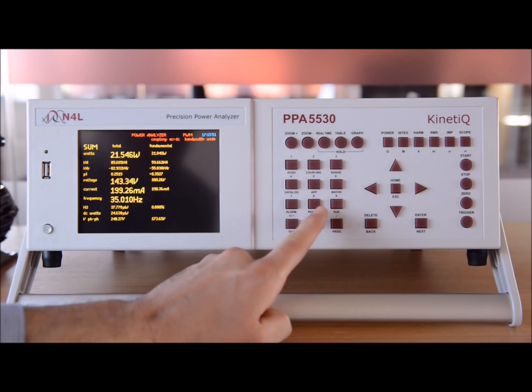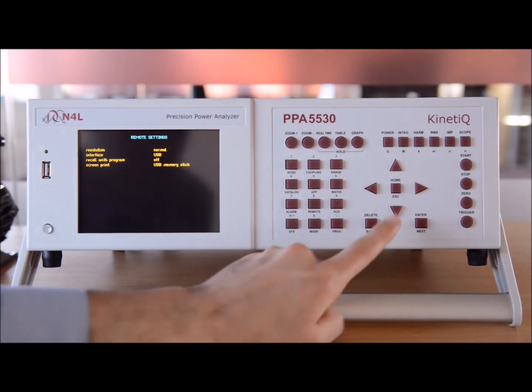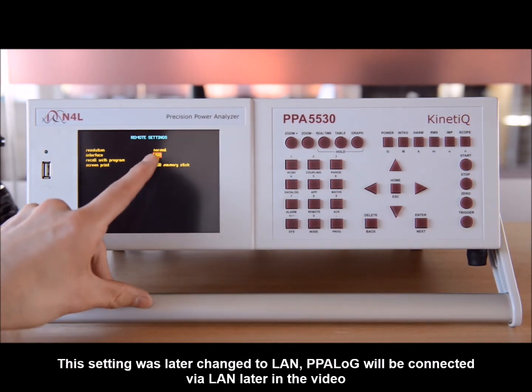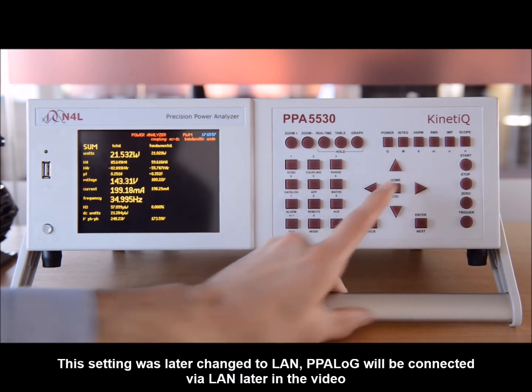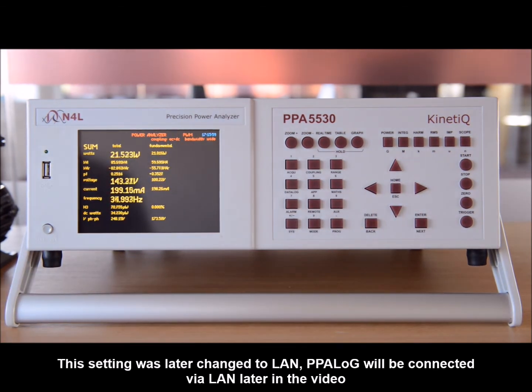So I need to make sure that my comms are set up for the medium I'm going to use. I'm going to use USB, which is fine, and you won't be able to see this, but I'm just going to make sure the other instrument's in USB, which it is. So now we are ready to connect to the software and perform an efficiency measurement from single phase input to three-phase output of a PWM motor drive.